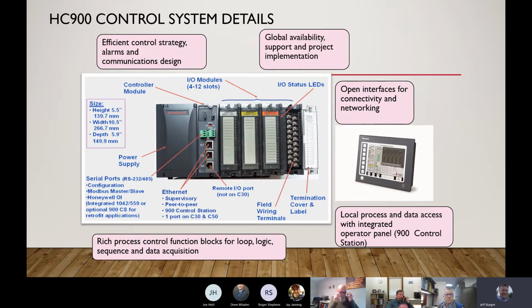You can also use it for peer-to-peer communications. So if you had several HC900 CPUs out on the plant floor and you wanted to share information back and forth between processes so the operator could see all that data on one display, you can have the peer-to-peer communications accomplish that for you. In addition, on that same port, you can also have an HC900 control station, which comes in either 10-inch or 15-inch, hooked up to that port, which would allow communications of all the process variables, alarms, diagnostics, things like that, that communicates up to the local display.